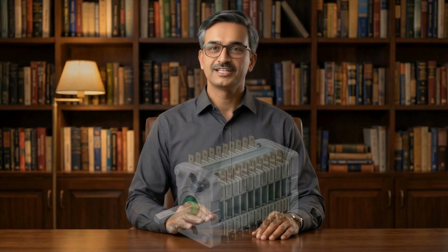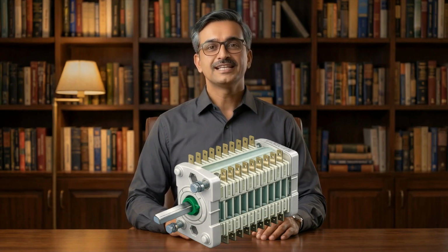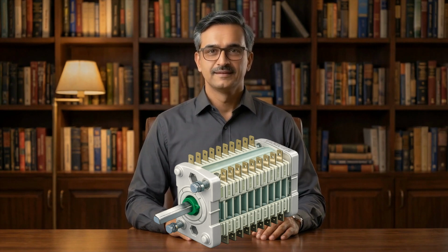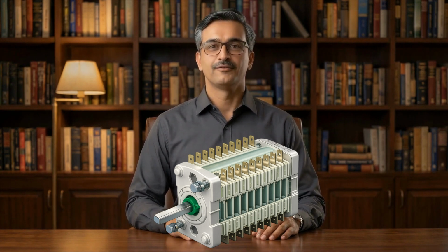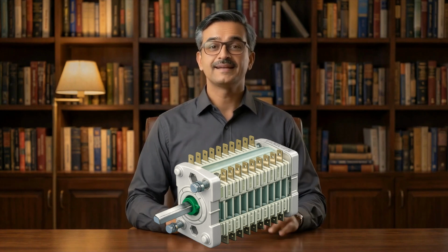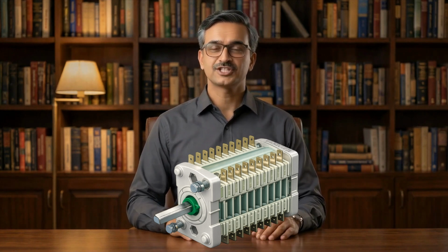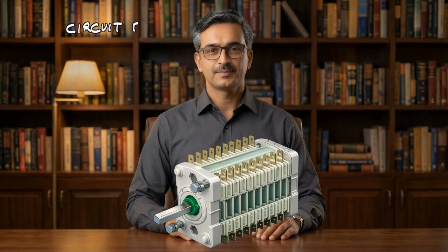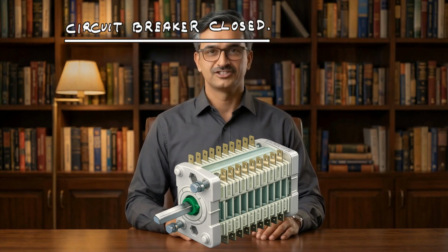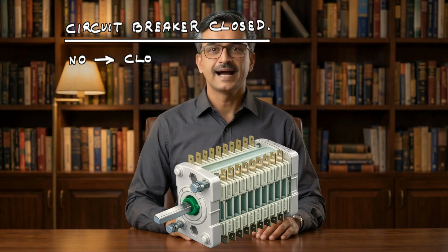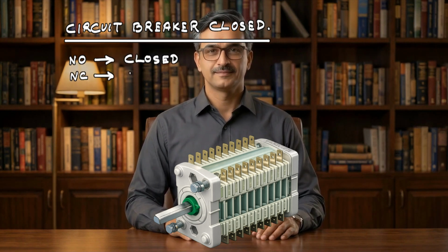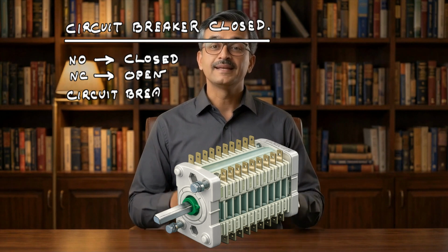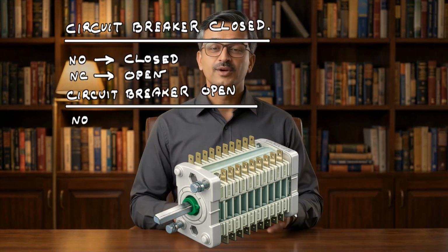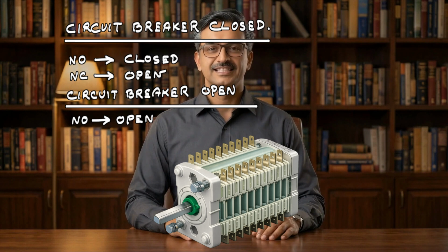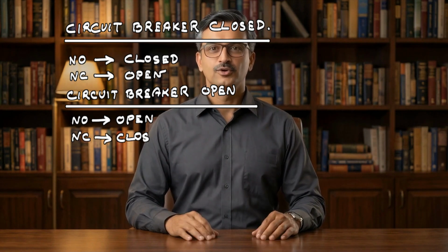Now, for each pole of the circuit breaker, an auxiliary switch is provided. This auxiliary switch is a mechanically coupled rotating switch. It is connected with the operating gear of the circuit breaker pole in such a way that when the breaker operates, the switch shaft also rotates. So when the breaker is closed, the NO contacts of the auxiliary switch become closed and the NC contacts become open. Again, when the breaker is open, the NO contacts return to their original open condition and the NC contacts return to their original closed condition.